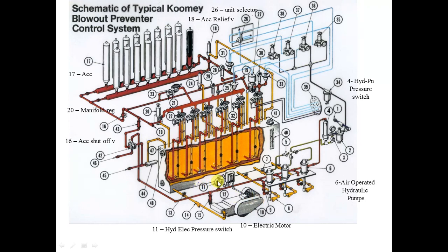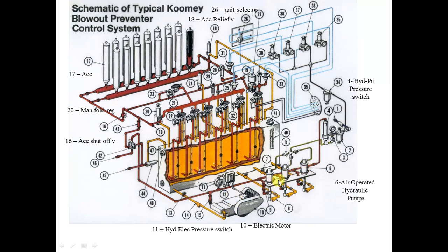Number eleven is the automatic hydroelectric pressure switch. For the air pump switch (number four), it starts at 2700 psi and stops at 3000 psi. Number eleven works similarly — it starts at 2700 psi and stops at 3000 psi. Both switches protect the respective pumps from overpressure.